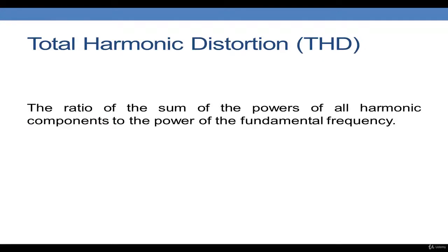Total Harmonic Distortion, or THD, is a quantity used to measure distortion in a power system. It is the ratio of the sum of the powers of all the harmonic components to the power of the fundamental frequency. Having covered the fundamental theory of harmonics, we will now enter ETAP to conduct a harmonic analysis.